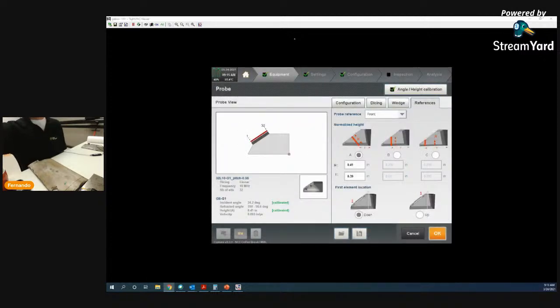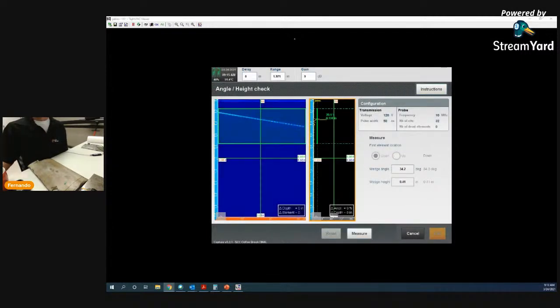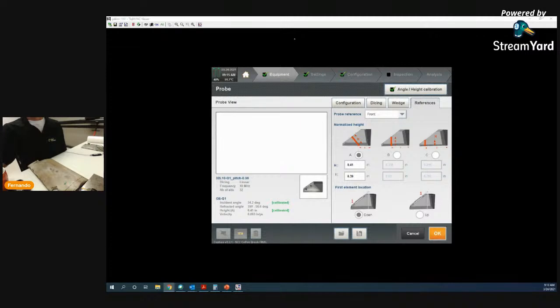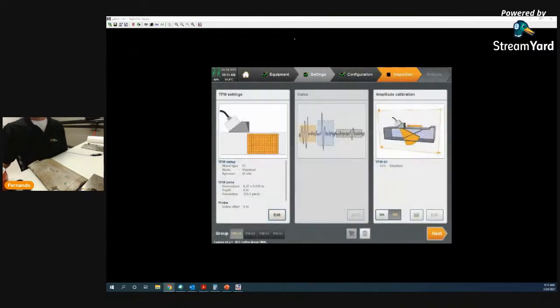So here's the other thing. I can choose the probe reference, and then I can go angle height. What this actually does is it calibrates the wedge delay without using a side drilled hole. The only thing that you have to do is pick up the signals, make sure you have a uniform signal across the screen, and hit measure. As you can see, the incident angle was originally 36 degrees, but now it's 34. So that's good. You can actually calibrate the entire wedge. So I'm gonna hit OK.